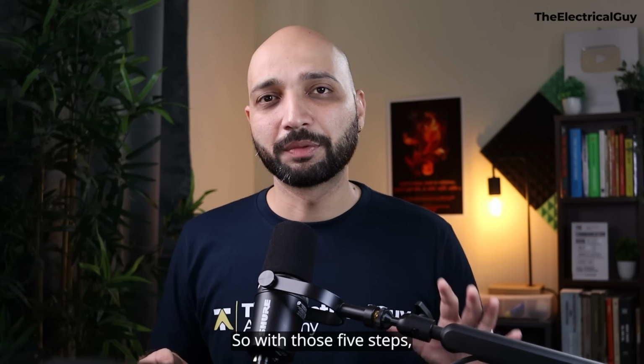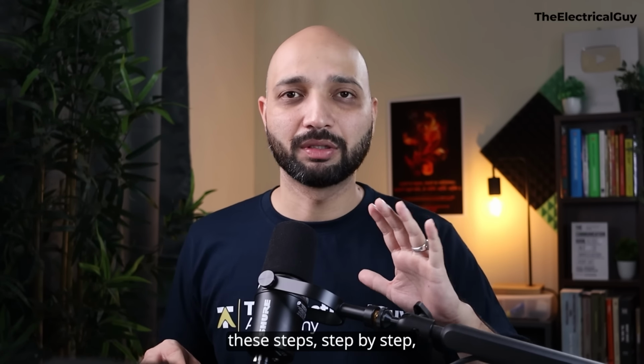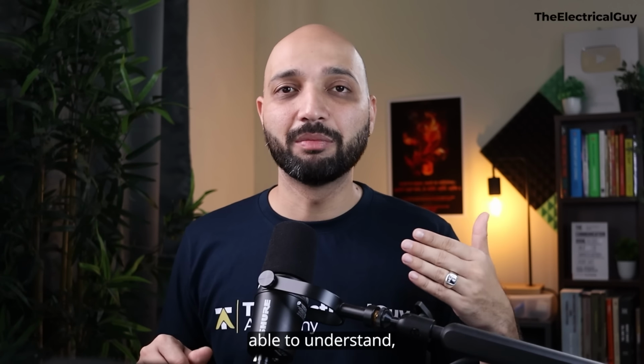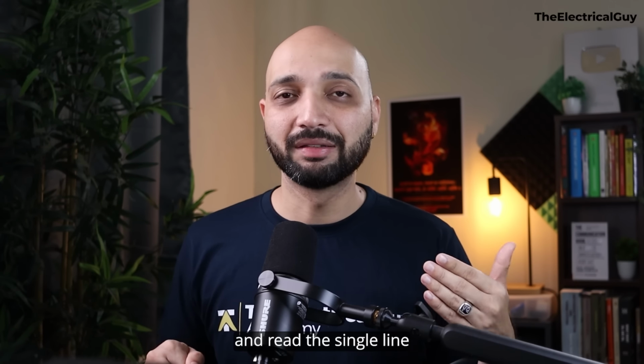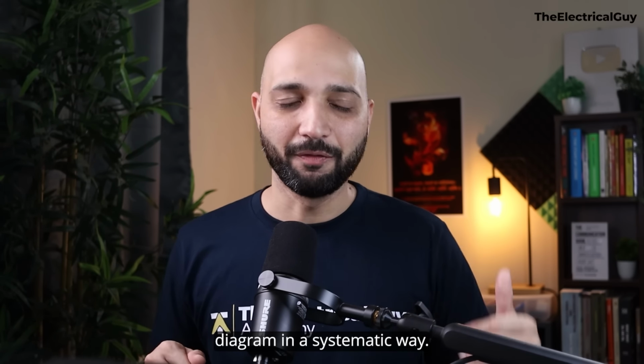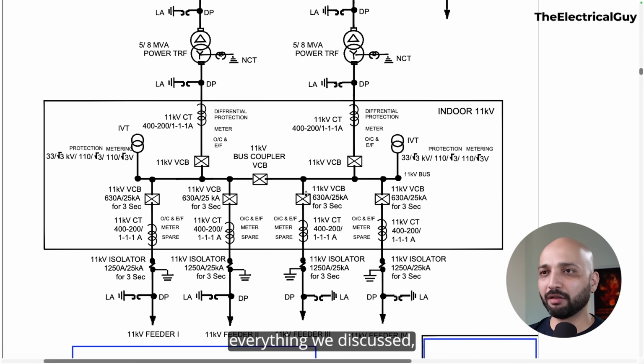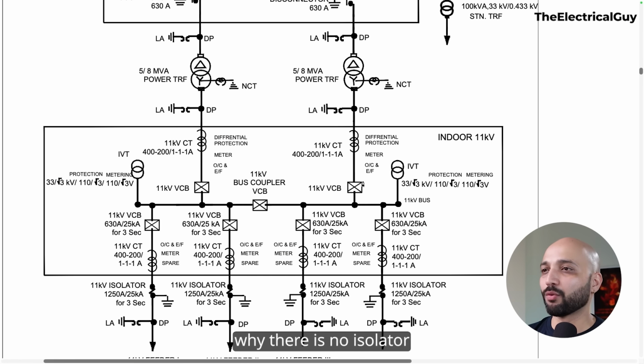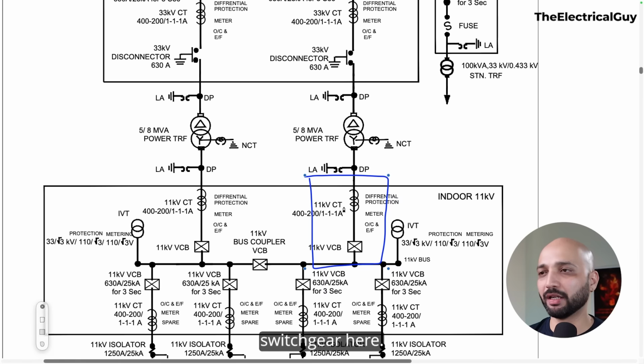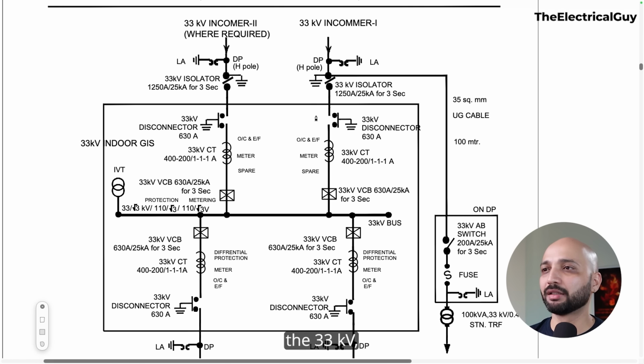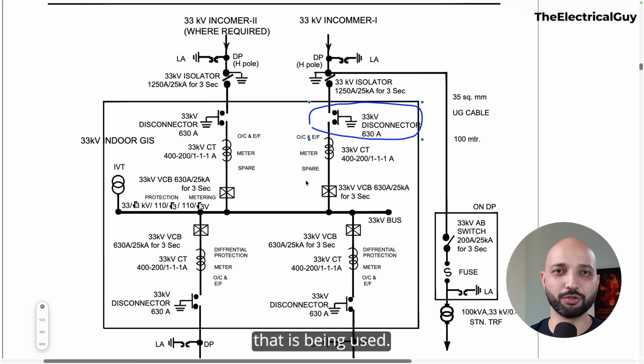So with those 5 steps, if you follow them step by step, then you will be able to understand and read the single line diagram in a systematic way. Now, everything we discussed, the question is, why is there no isolator used in the 11 kV AIS type switchgear here? Whereas if we see the 33 kV, we have a dedicated disconnector that is being used, right?